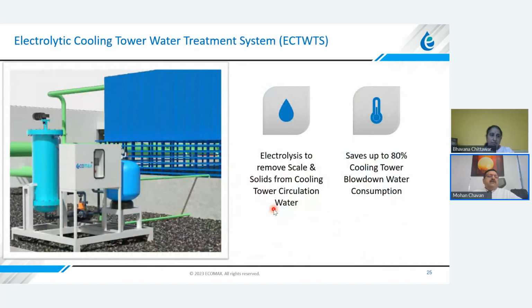The second technology that we are talking about now is the electrolytic cooling tower water treatment system. Okay? This is again a chemical-free solution that is helpful for treating the cooling tower circulation water, and it's basically based on the electrolysis of the water. It removes the scale from the cooling tower sump water, and that's how we're able to save up to 80% blowdown water consumption. This is the cooling tower, and this is installed in the side stream.